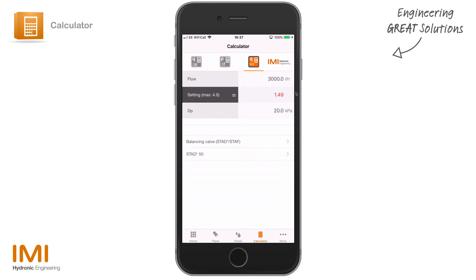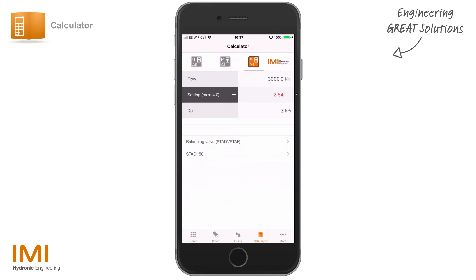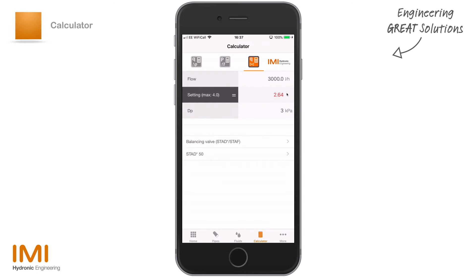It's determining that the valve setting should be 1.49 for 20 kPa. Now let's say we want just 3 kPa — perhaps this is our index valve and we want to determine what the pre-setting should be. If we change that to 3 kPa, the pre-setting for the valve should be 2.64 — that's 2.64 turns out of 4, which is the maximum number of turns on a STAD.